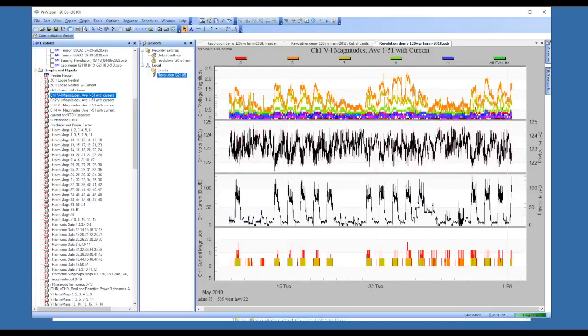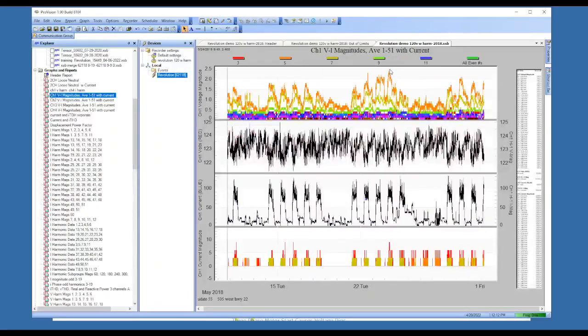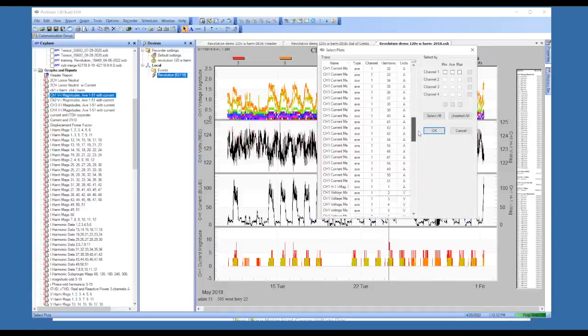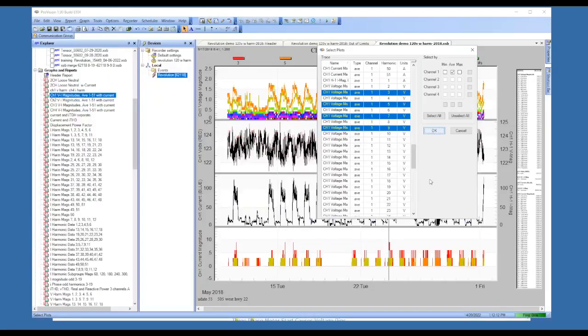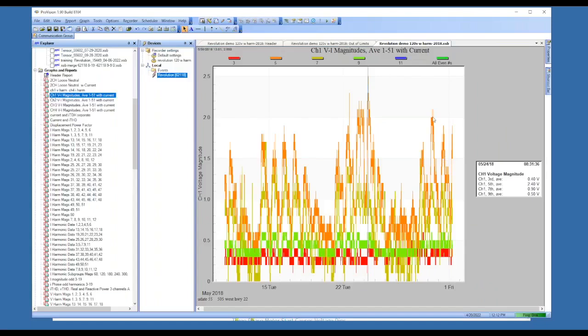And that's really why you don't need to record the first harmonic. They should be exactly the same as the voltage and the current. And then you have your current harmonics here. The toggle point table does work on these also. And it'll show you all the harmonics that are there. Again, you can go under the select plots and just choose a few of these, if you just want to look at a few odd ones. So it's an easy way to break them down pretty quickly.